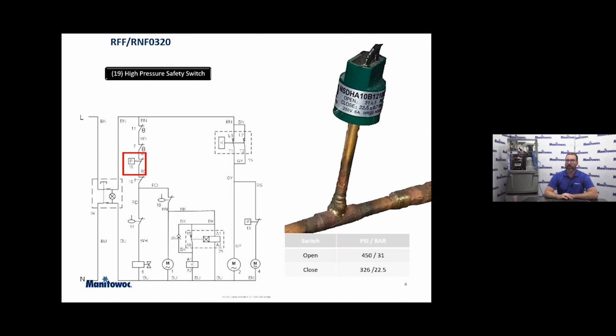Pay attention to the fact that these would be for 404 based systems. The pressures that are going to be on a propane-based system are going to be different, of course. So we always want to pay attention to what kind of system we're working on. Now, if we need to know exactly what those pressures are, we can always find those pressures in our technician's handbook. Those are always listed in there, and they'll be pertinent to the model number of the machine that you're working on. You'll also notice in this particular instance, you can see the pressures open and close right on that pressure switch itself.